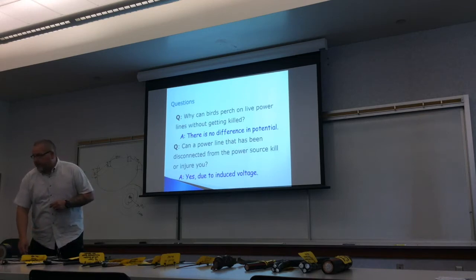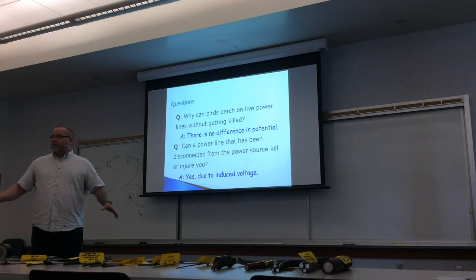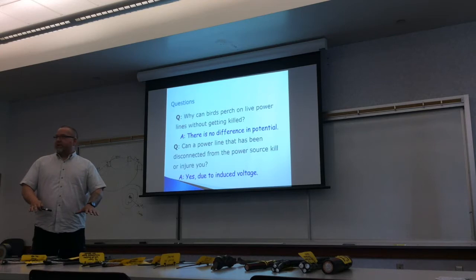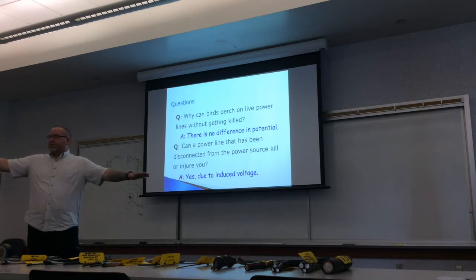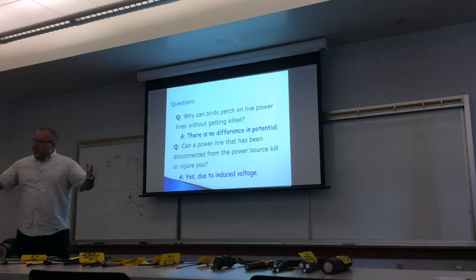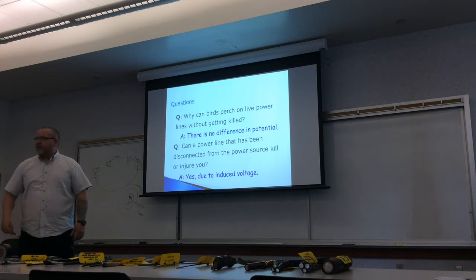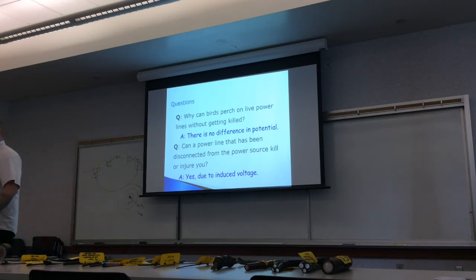That's what happened to the firefighters I told you about before. They were on the ground, the ground was wet, a wire hit the ground and energized it, creating a ground gradient. They were standing with their feet apart, basically getting a brand new electrical circuit every time they took a step.